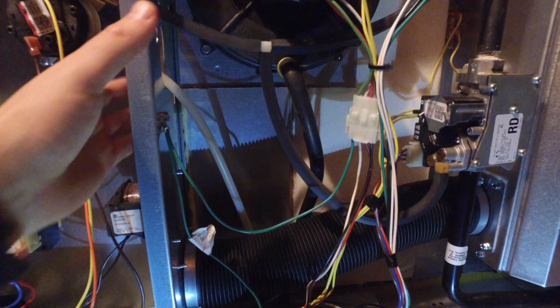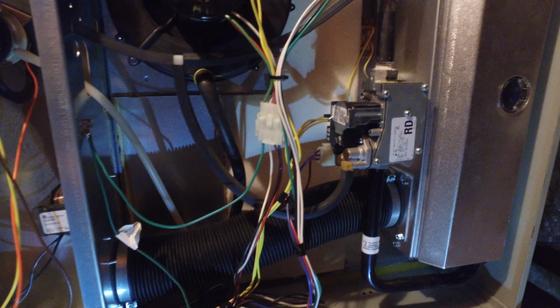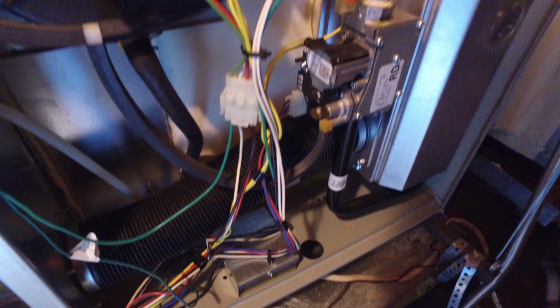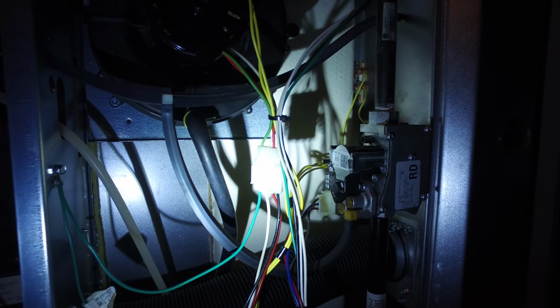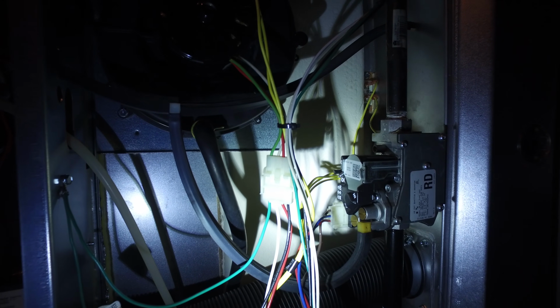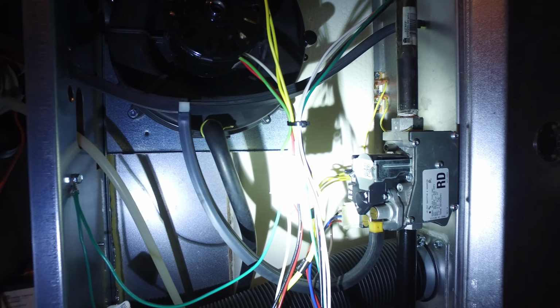So we drained this little line right here a few times. Then we disconnected this right here, and he came over here to this pipe and cut it. He brought some pressurized nitrogen up here and shoved it into that pipe, basically blowing it out because it was clogged. What was happening was when he had this line off and was blowing into it, he couldn't actually blow - he could feel the blockage in this line. So that's how we determined it needed to be blown out fully, that there was some sort of a clog.